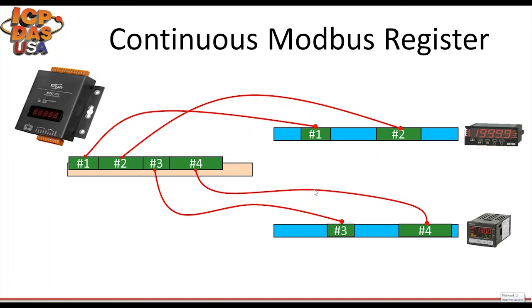As you can see from the slide, the Modbus data of some Modbus RTU devices are not stored continuously. In conventional communication, the computer will send multiple commands to read Modbus data, and if it requires reading or writing data several times, the efficiency and communication speed will be very slow. The Modbus Data Concentrator will organize the data from multiple RS-485 devices to be stored continuously, no matter if the original data is continuous or not. This way, the PC can read large amounts of data at once and increase the efficiency of communication.